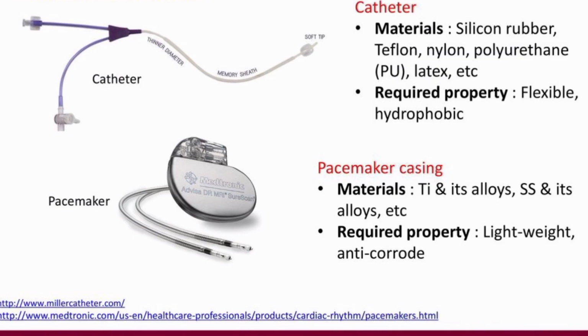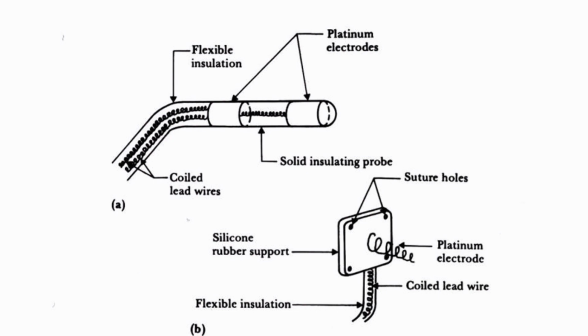The casing of a pacemaker is made up of metal like titanium, though polymers are also a critical material for pacemakers. Blood compatibility is one of the major criteria which limits the use of biomaterials for cardiovascular applications. The metal lead of a pacemaker is made up of metal alloy but is insulated in a polymer such as polyurethane.